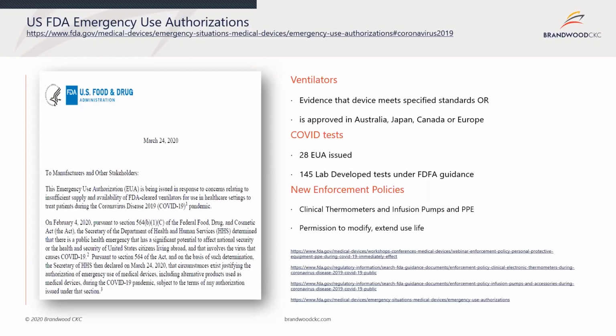And a couple of new enforcement discretion policies were issued. FDA is putting out quite detailed guidances on clinical thermometers, infusion pumps, and personal protective equipment, around what's permissible and what extra wiggle room manufacturers and suppliers have got. Things like changing design specs of devices, changing manufacturing arrangements, changing critical suppliers, without the normal need to go through the long-winded variation applications where you've got to put in a new 510K or a variation of a PMA or whatever for some of these devices.